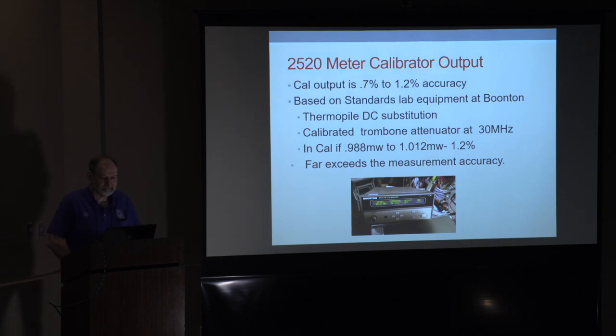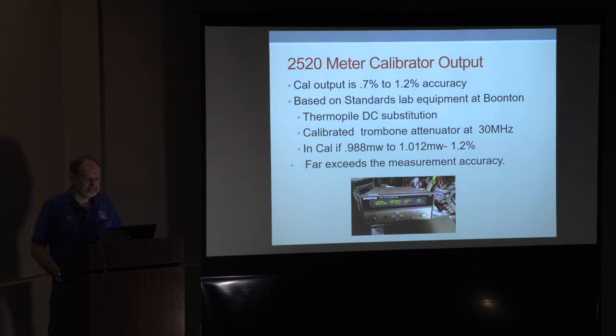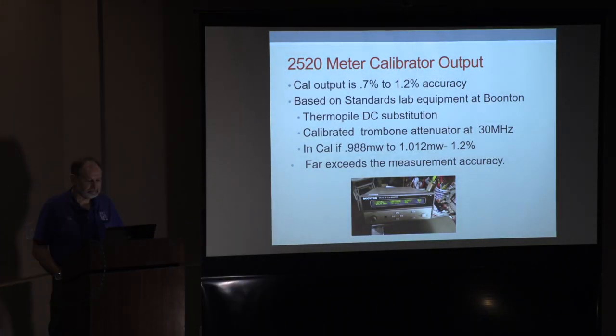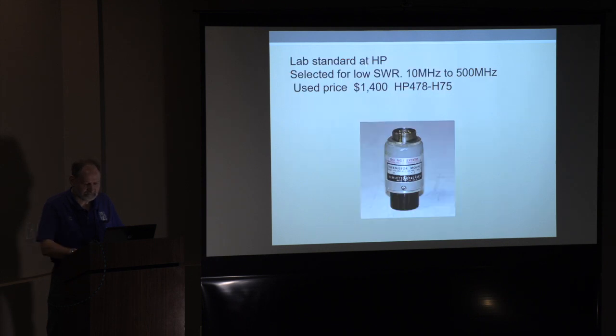Okay, the output of the 2520 is from 0.7 to 1.2%, which is 0.05 dB. It's based on some really nice standards at Boonton, and you can see the milliwatt difference. If you are within that range, you're within 1.2%. Okay, next slide. Here's the 478. This is not, I don't think it's an H75. The metrology grade ones look just like the other ones, except they say H75 on them.